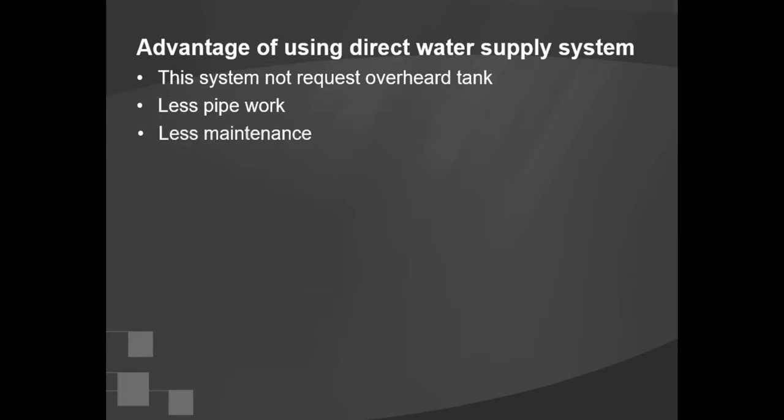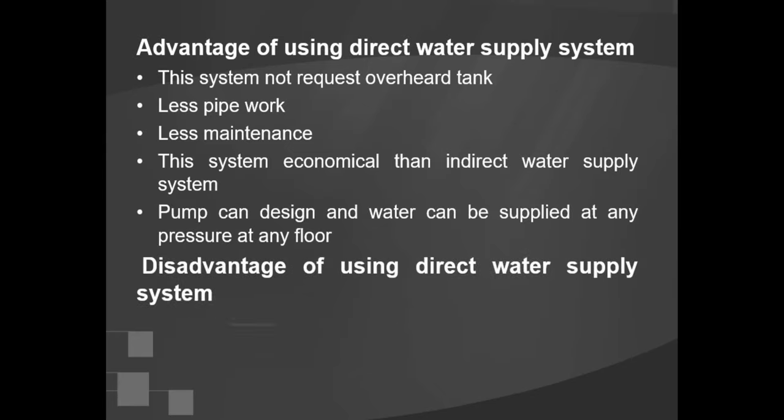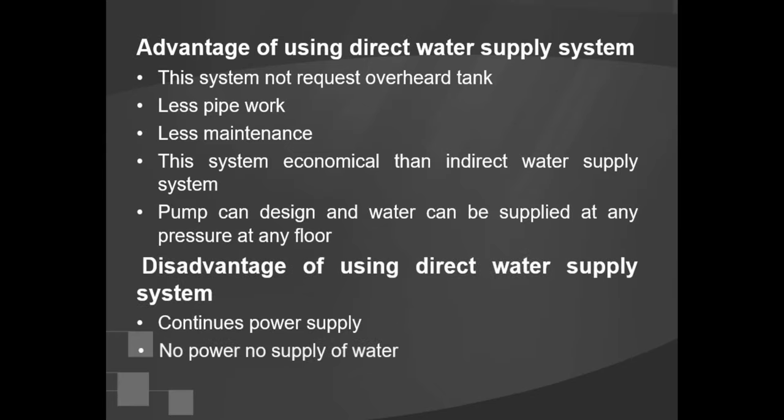Advantages of using the direct water supply system: this system does not require an overhead tank, involves less pipe work, requires less maintenance, and is more economical than the indirect water supply system. Water can be supplied at any pressure to any floor. Disadvantage: this system requires a continuous power supply — when there is no electricity, water cannot be supplied.